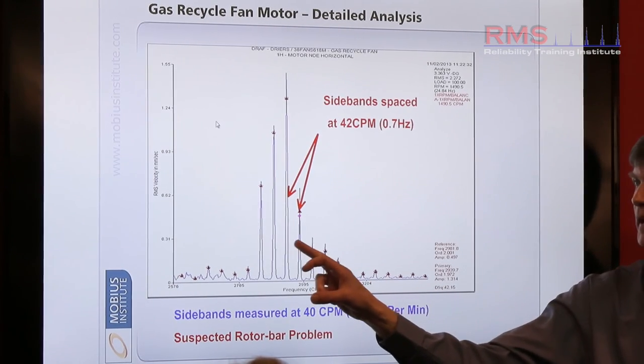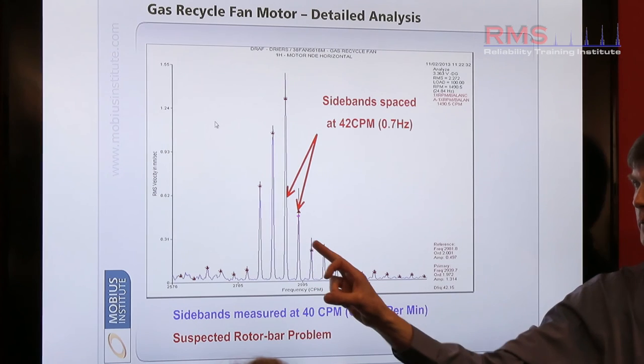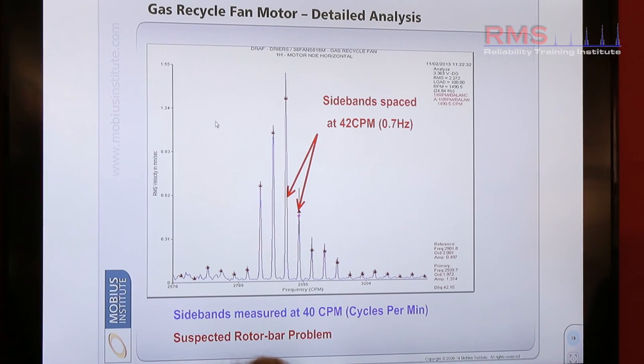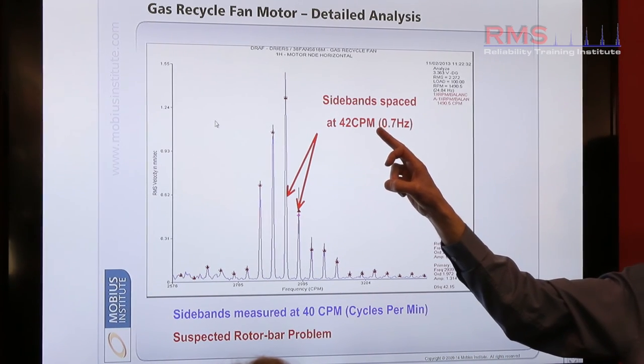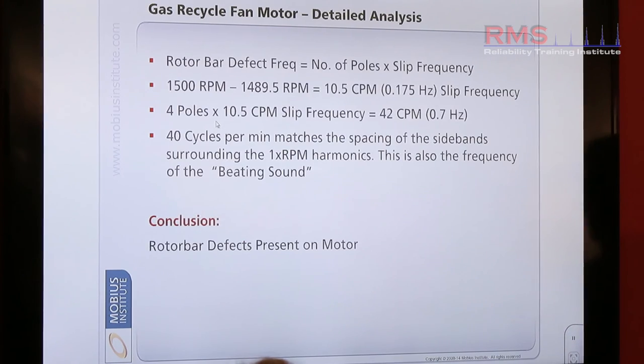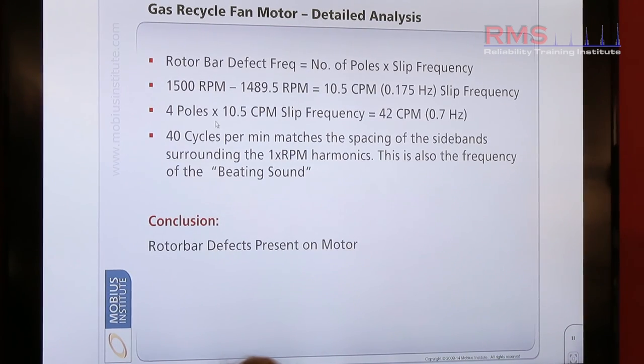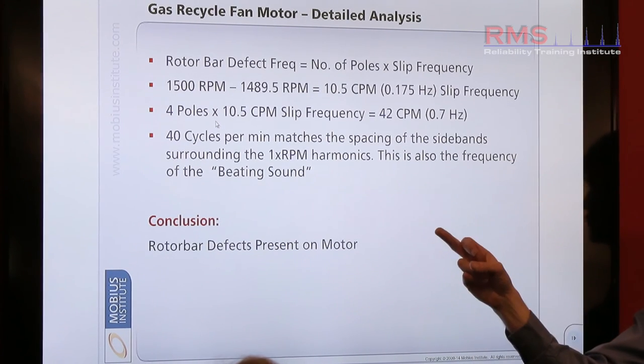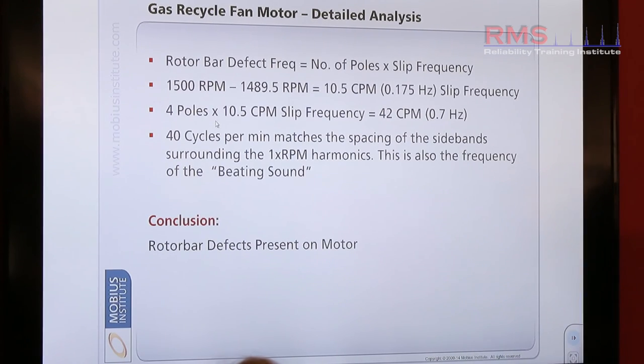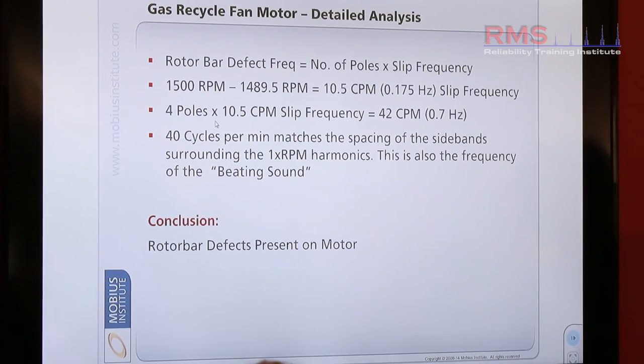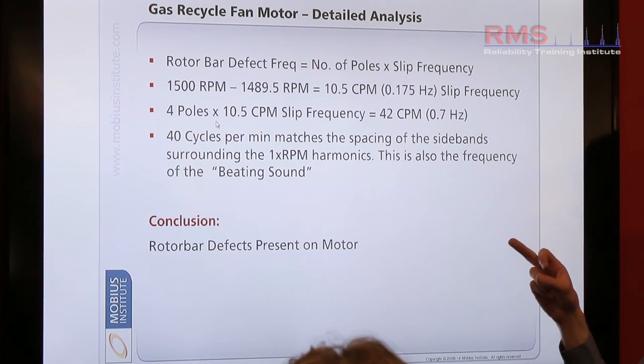The spacing between the central peak and the peak spaced equally to the side — the delta frequency — was the key. The spacing was 42 cycles per minute, or 0.7 Hz. And then with some known mathematics — which to be fair the software today deals with for you anyway — mathematically this tied down to a rotor bar problem. Not a bearing problem, not a balance problem, not an alignment problem, but a rotor bar problem.